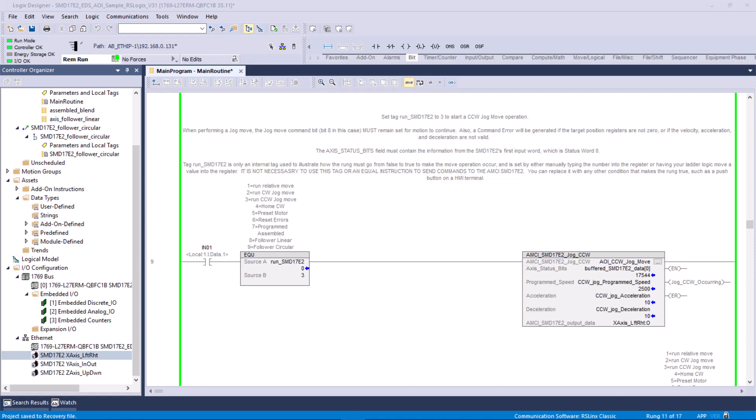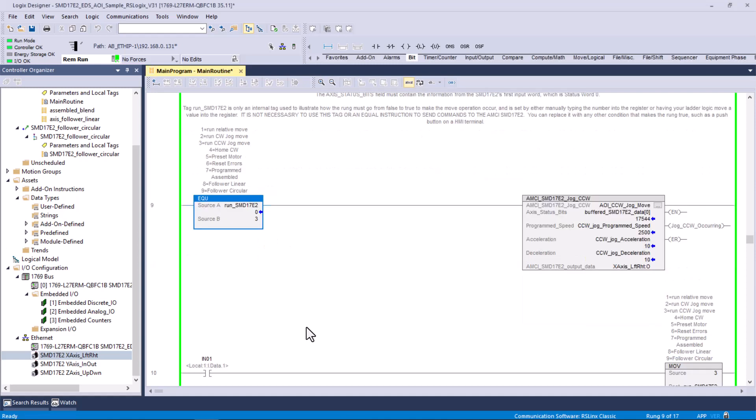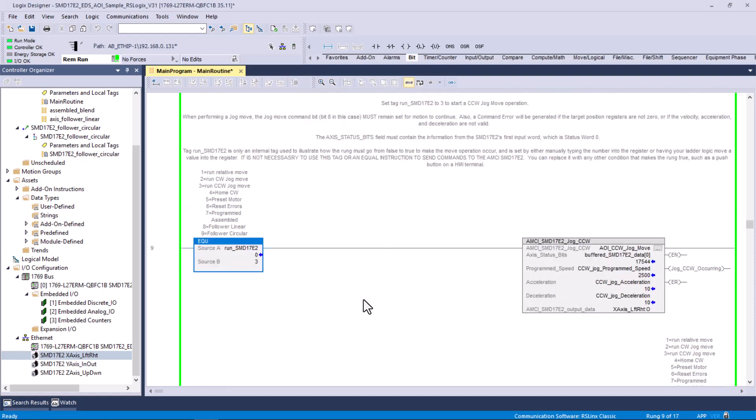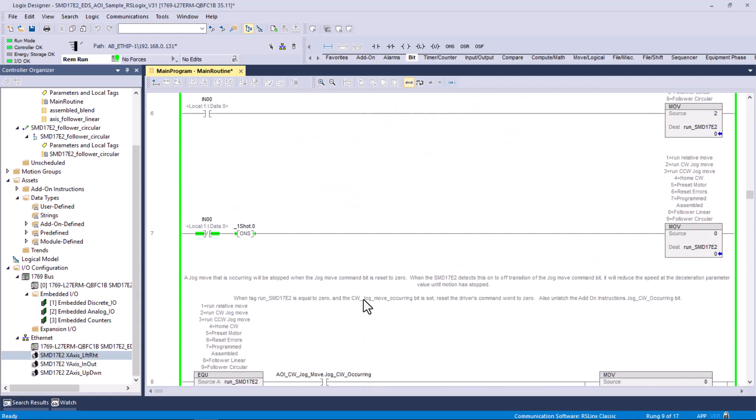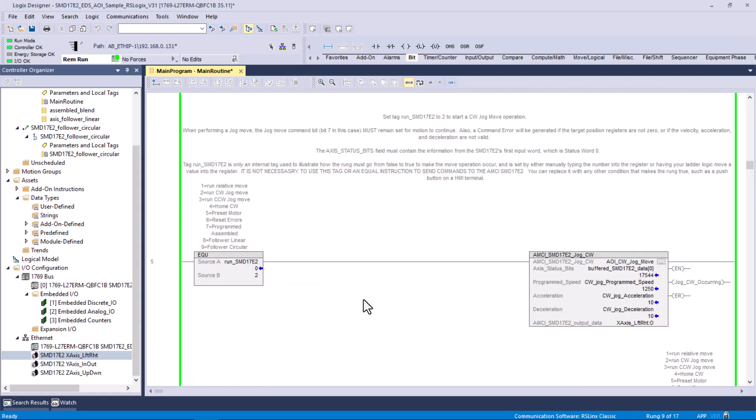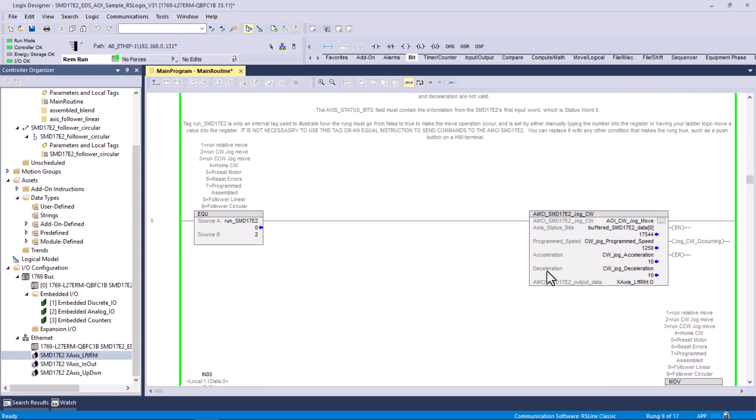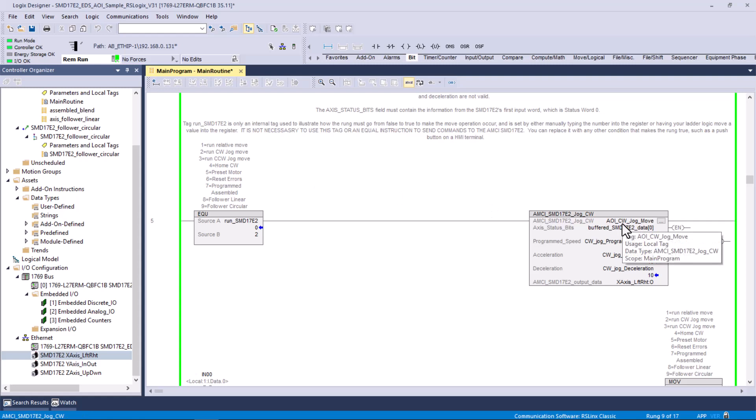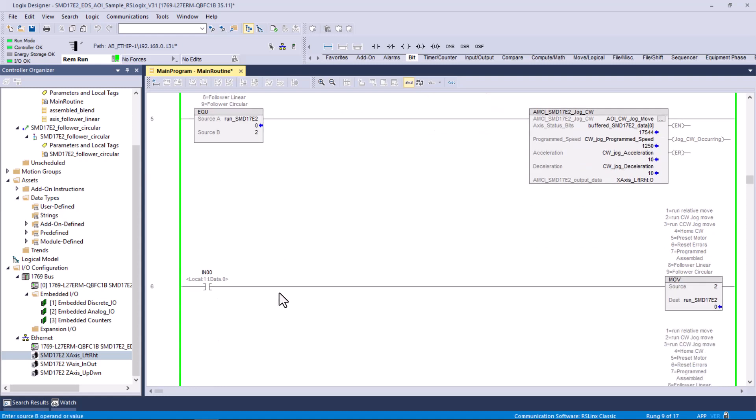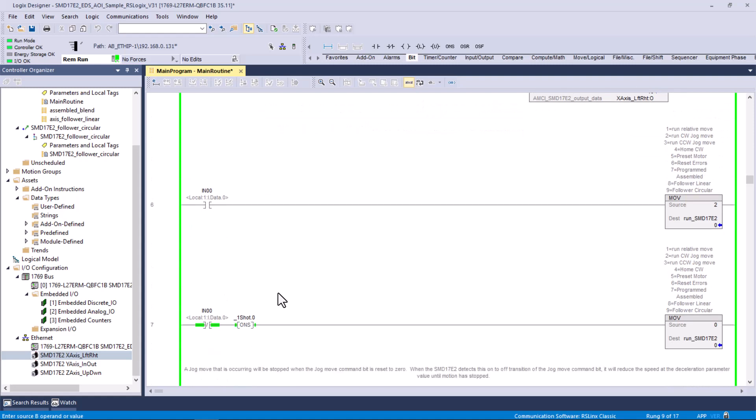I went through and I changed the tags on this sample program from AMCI. The next thing I did was to go in and add some logic. What I wanted to do is I wanted to be able to jog it. I went to the jog instructions. Remember, these are add-on instructions that were created for or by AMCI. And this rung says, and here's your codes here, if you like, one through nine. And of course, zero means don't do anything. Two is run clockwise jog, and three is run counterclockwise jog. You see that this is a clockwise jog move, and so we need to get a two in here. And when we get a two in there, then it will run clockwise.